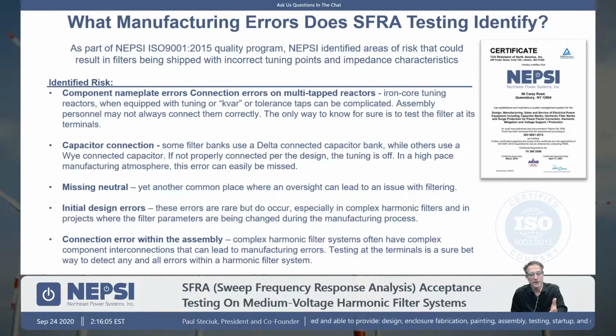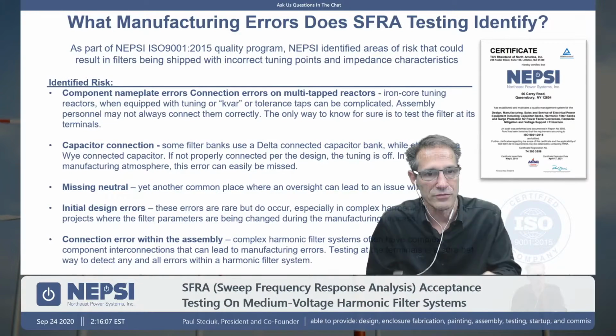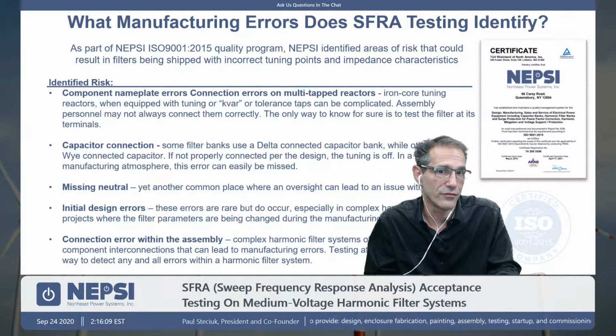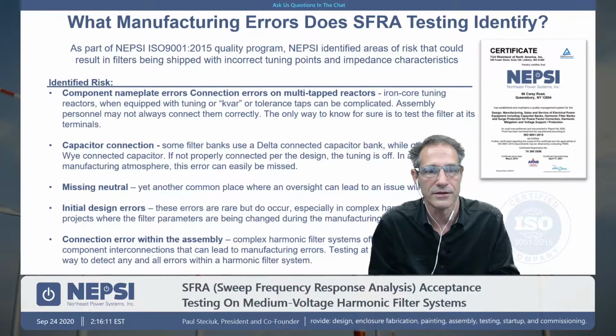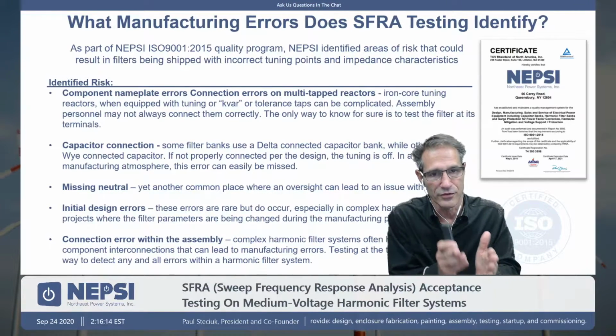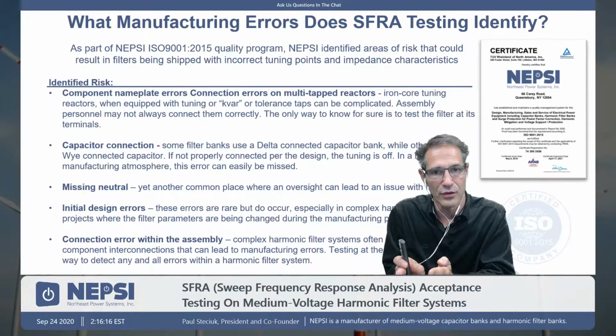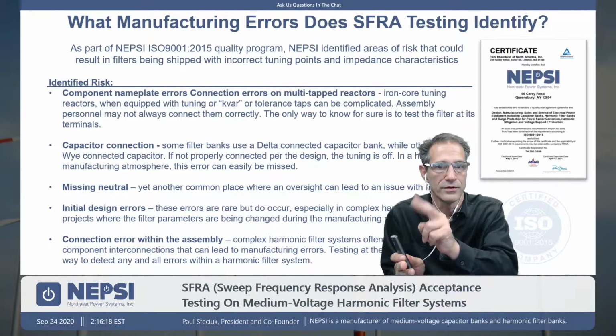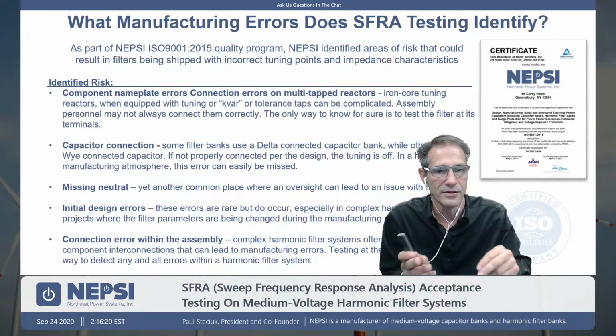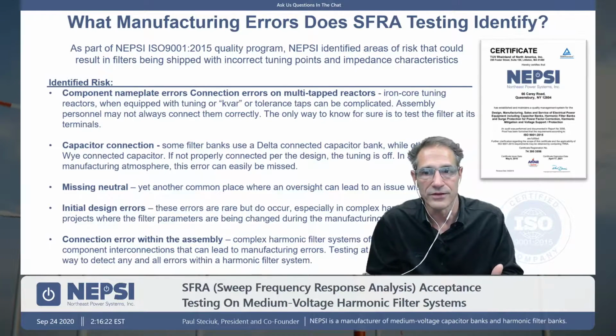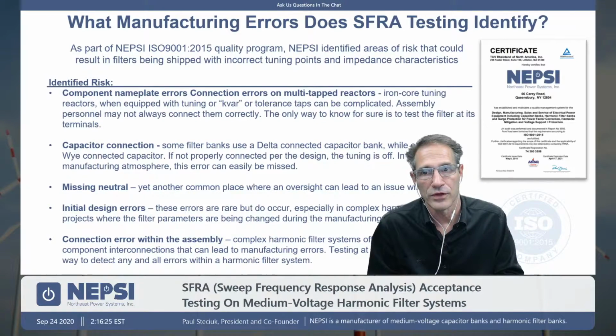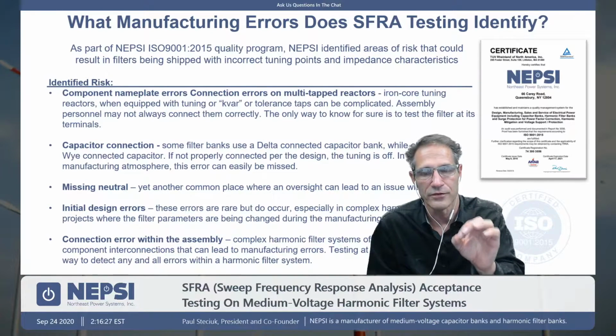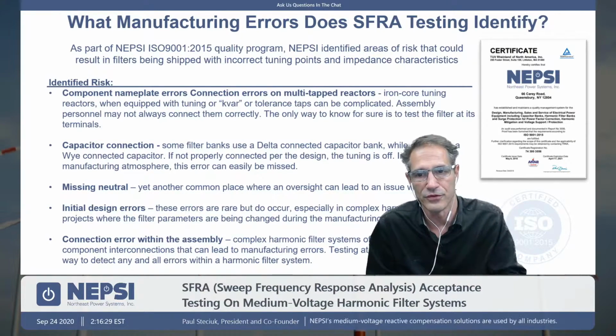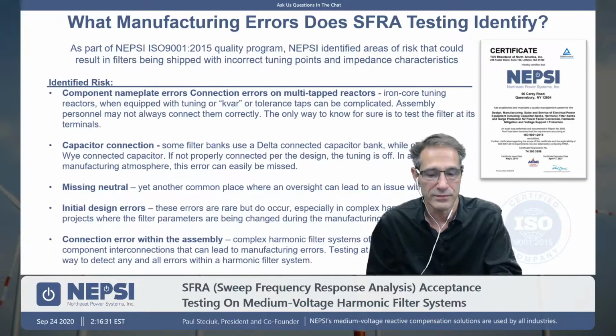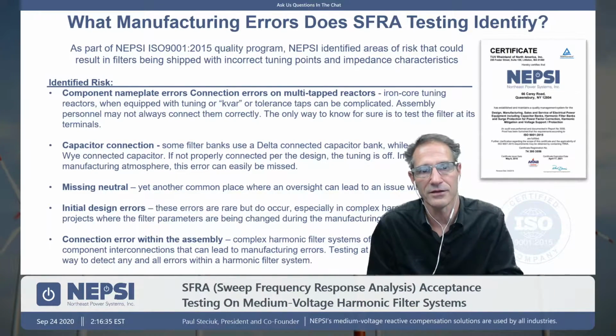But this test makes an assumption that everything was manufactured properly at the factory, and the reality is it might not have been. You want to have some other device connected external to the equipment that looks into the equipment and checks everything, all the connections. You know, has the neutral been connected, things like that. So we're looking for all types of errors that might have occurred, and this helps to ensure that you as a customer, or you as an EPC who has come up with a filter design, are getting exactly what you asked for.